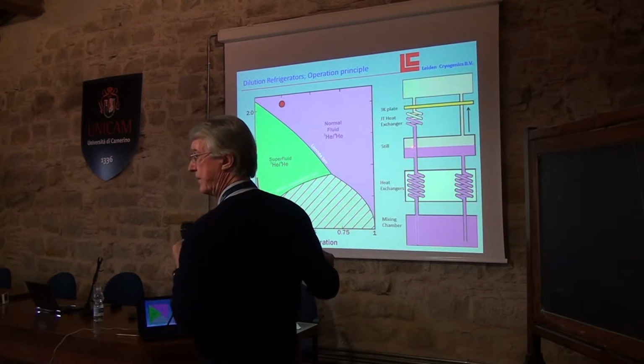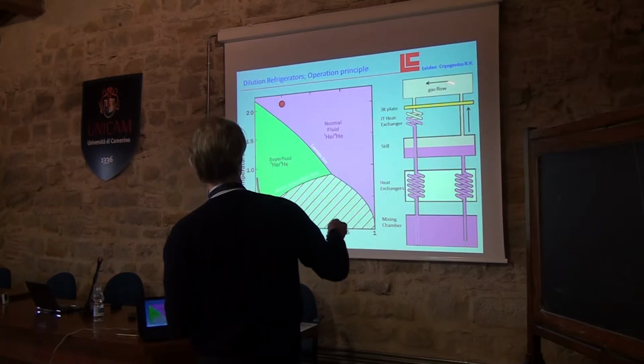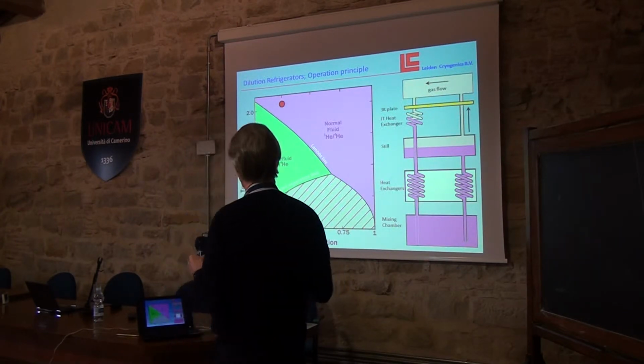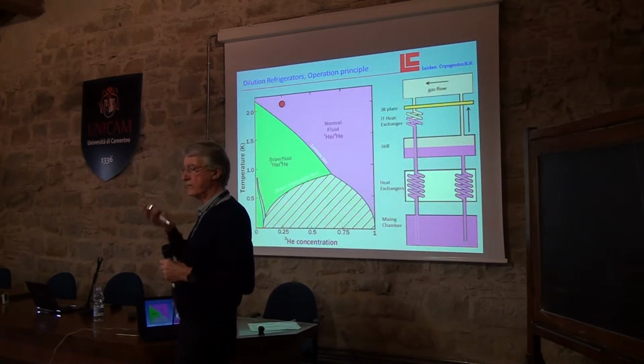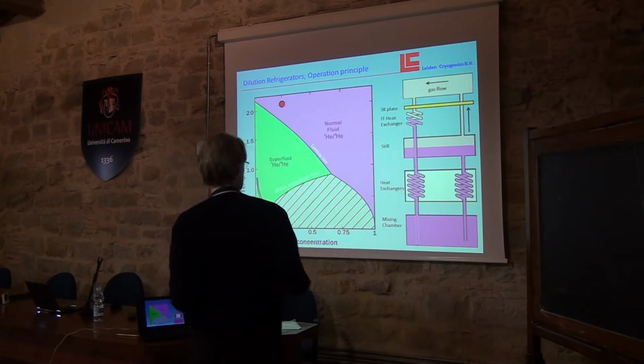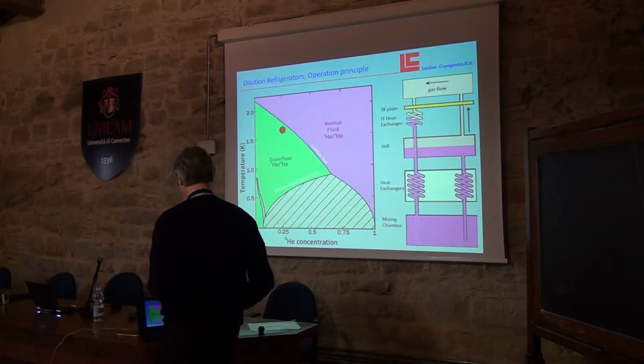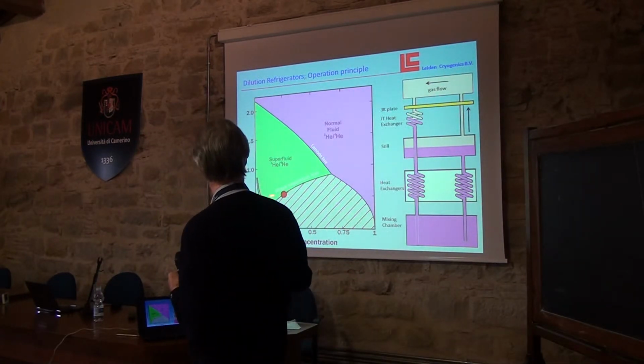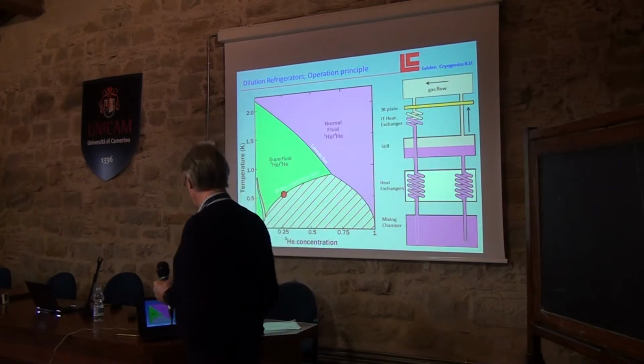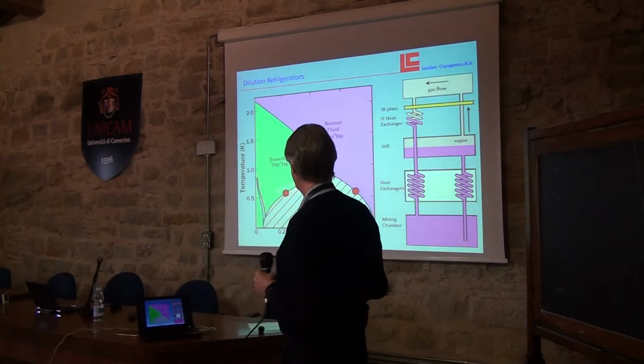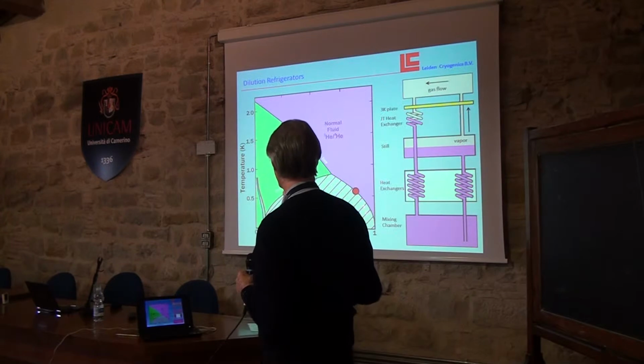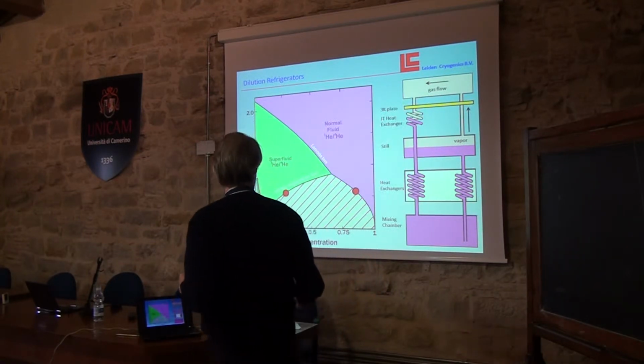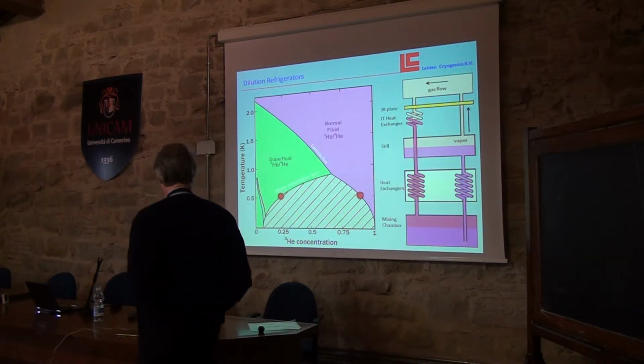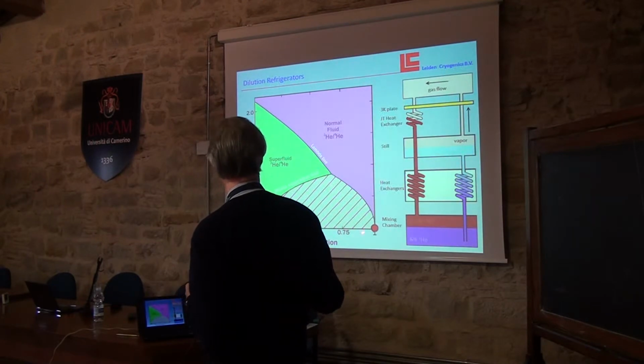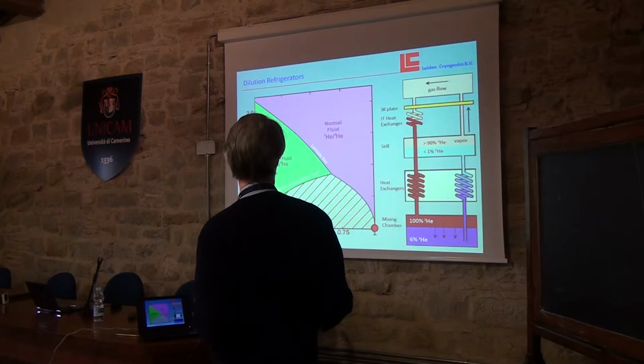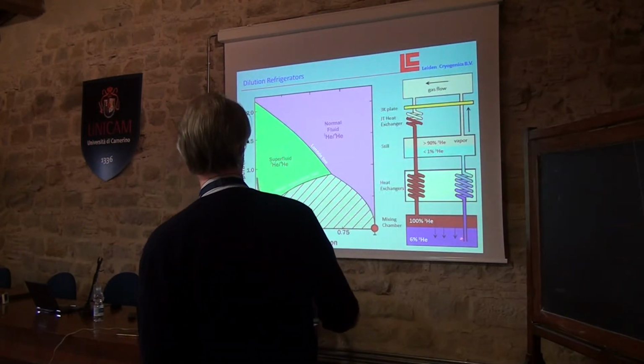Here you have the liquid-gas phase transition. And here you have a pump at room temperature that starts circulating this mixture. Because helium-3 has a much higher vapor pressure, what you do is you distill helium-3 out of helium-4. So the temperature goes down, and at this point, depending on the concentration, you get a phase separation. One side is essentially low concentration of helium-3, the other side goes to extremely pure helium-3. And if you keep pumping, this is what happens. You get this 100% helium-3 and 6.5% helium-3 in helium-4. And here is your pure helium-3, and this is the dilute phase.